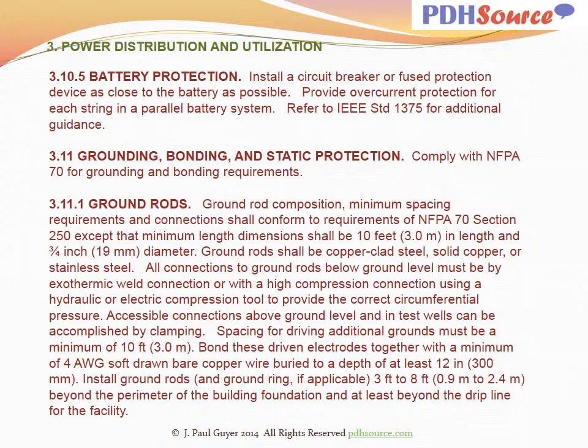For ground rods, ground rod composition, minimum spacing requirements and connections shall conform to the requirements of NFPA 70 section 250, except that minimum length dimensions shall be 10 feet in length and 3/4 inch diameter. Ground rods shall be copper clad steel, solid copper, or stainless steel. All connections to ground rods below ground level must be by exothermic weld connection or with a high compression connection using a hydraulic or electric compression tool to provide the correct circumferential pressure.